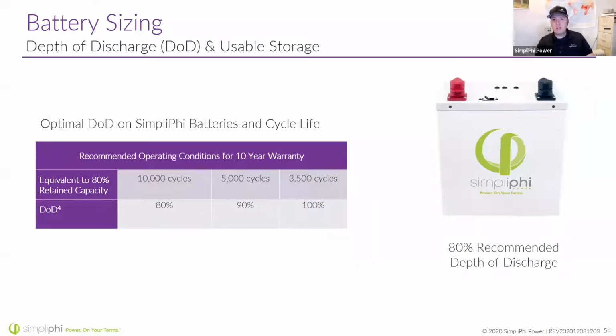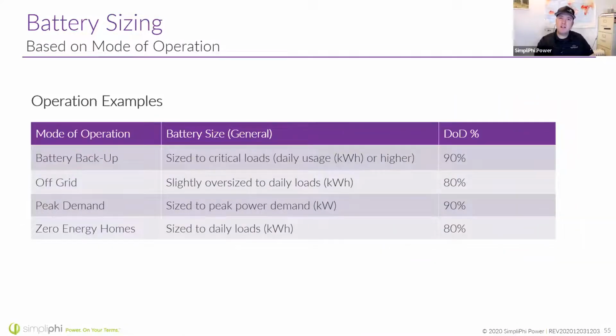There's 2 sizing things I want to talk about. One is sizing for capacity, or how much energy in kilowatt hours or amp hours you need for a system. When it comes to sizing, you can size to 100% depth of discharge, knowing you're going to use all of that 3.8 kilowatt hours in the Phi or SimpliPhi. If you're cycling the battery a lot, maybe it's on an off-grid home, maybe you're doing a lot of time of use arbitrage, let's size for an 80% depth of discharge. Only plan on using 3 kilowatt hours out of that 3.8, because we know that we're going to give that battery the most life after that 10-year warranty period. But if the battery is just sitting there waiting for an outage, or maybe just occasionally doing peak demand, having the 90 or 100% depth of discharge is totally acceptable.